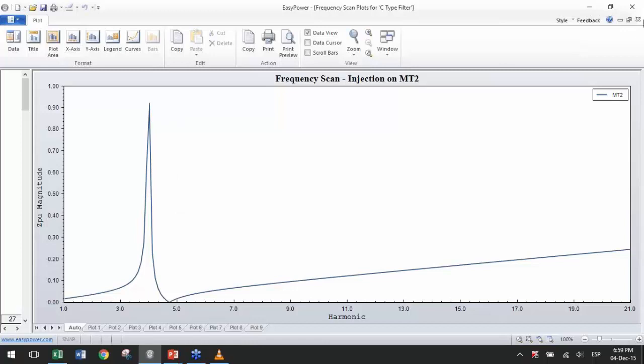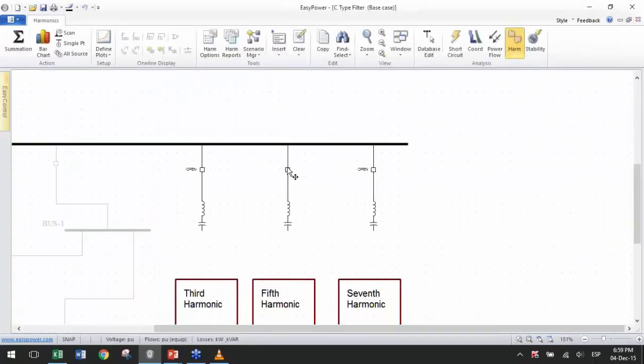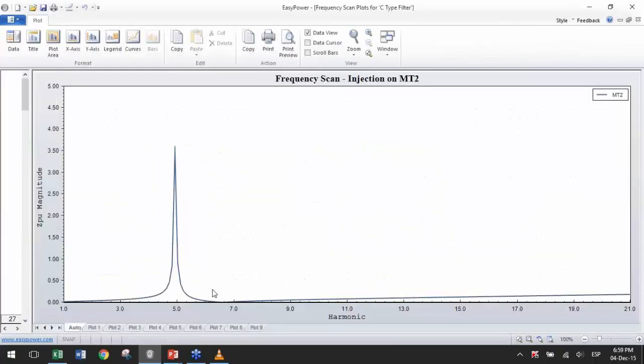It's a little lower. Now, let's try the same thing with a seventh harmonic filter. The resonance doesn't disappear from the system. It's still there. It's just a little lower. And this is a resonance that I definitely want to avoid, because it's right at the fifth harmonic, which is a harmonic where you normally have a lot of content, a lot of fifth harmonic because of the drives. So this is not a good solution.